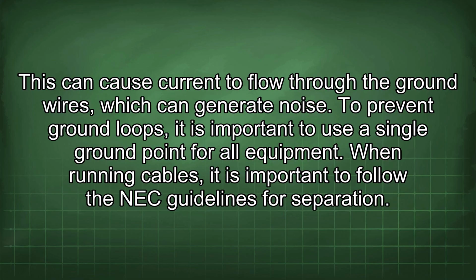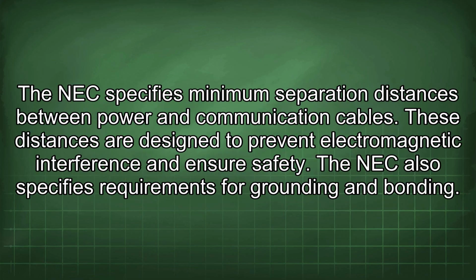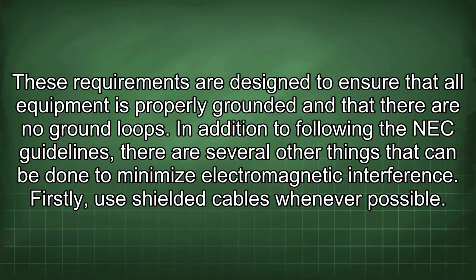When running cables, it is important to follow the NEC guidelines for separation. The NEC specifies minimum separation distances between power and communication cables. These distances are designed to prevent electromagnetic interference and ensure safety. The NEC also specifies requirements for grounding and bonding. These requirements are designed to ensure that all equipment is properly grounded and that there are no ground loops.